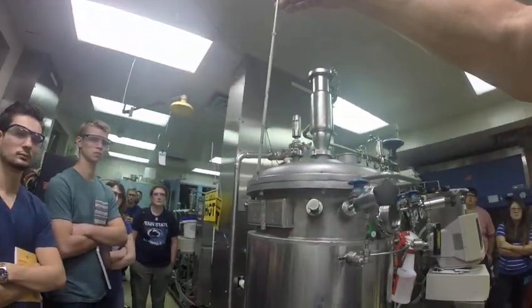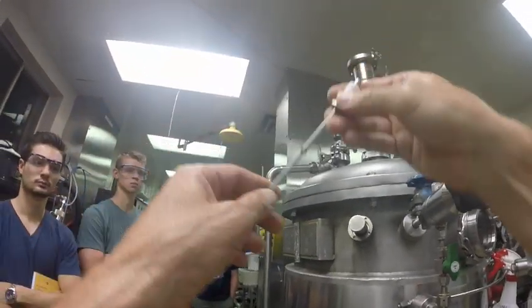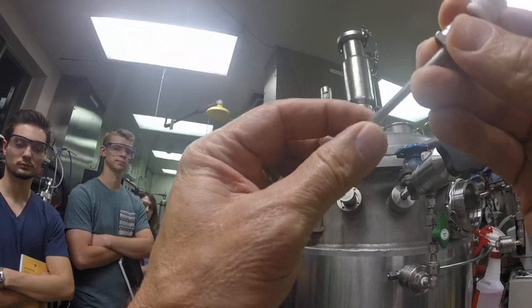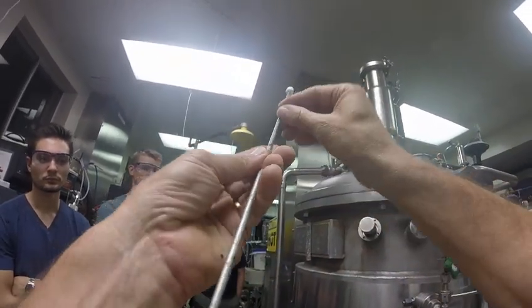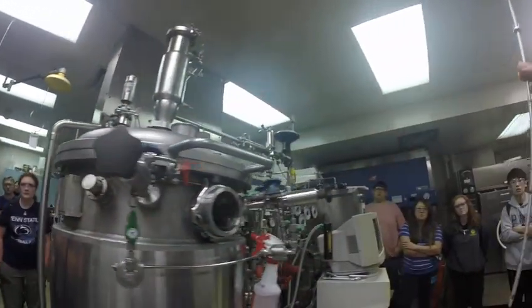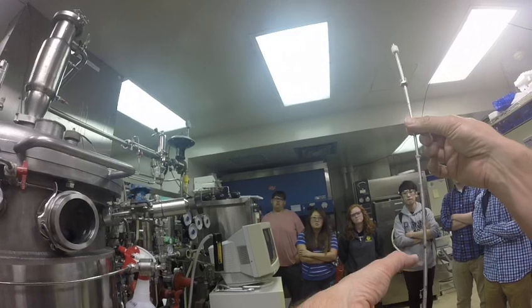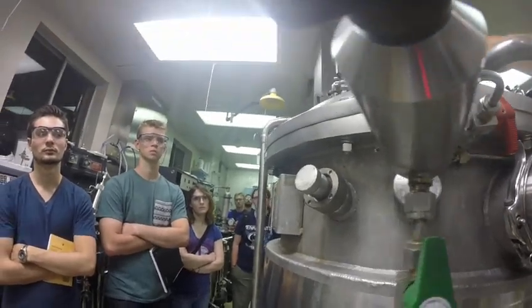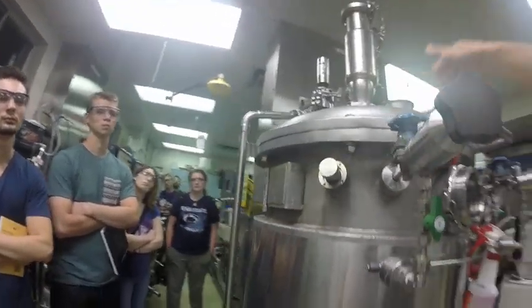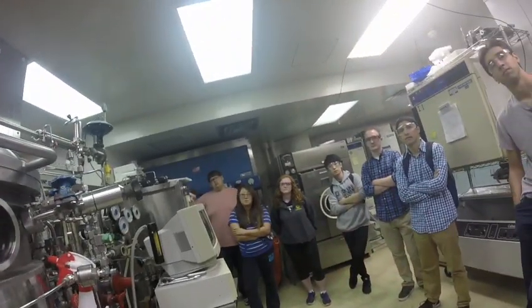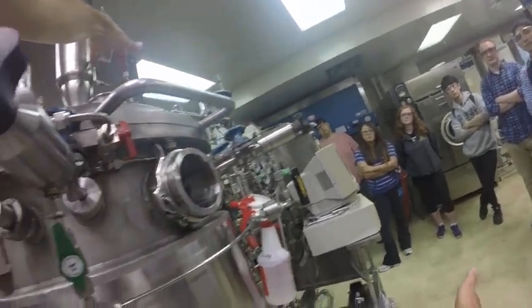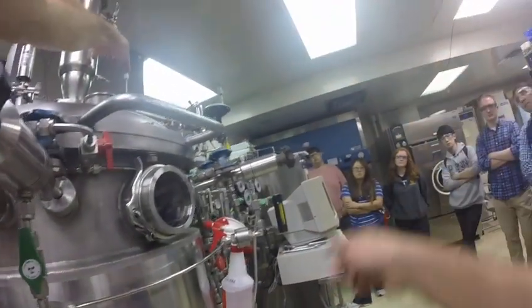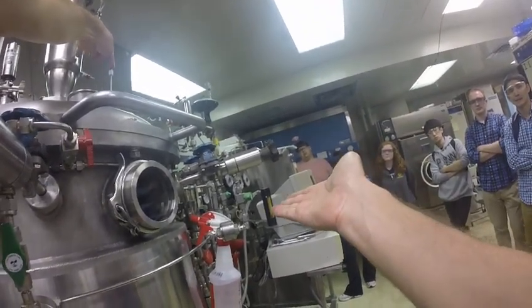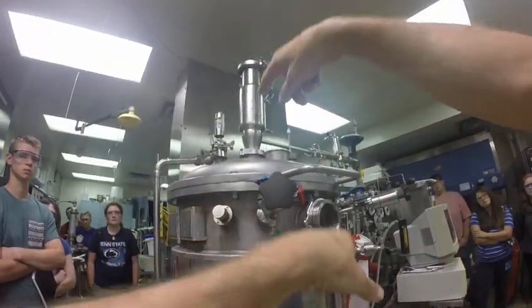If I put this inside the tank, you'll notice it has a gasket made out of a non-conducting material. If you look carefully, at the top it's actually plastic coated, but once you get further down it's no longer plastic coated. So there's no electrical contact at the top where it goes through the Swagelok fitting. If I put a small alligator clip here and measure the resistance between this point and any other part of the tank, the resistance will be infinite until the liquid makes contact with it. Once the liquid touches it, you get zero resistance, and you can use that to determine level height.